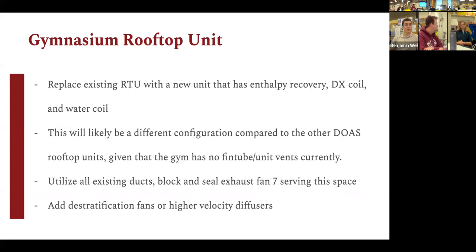So we propose adding that space also will probably have to have either higher velocity supply diffusers or destratification fans in order to get better circulation of the air in that space. And again, we're going to be sealing off the exhaust fan and just rerouting where there's already return ductwork going up to the roof for the mixed air damper. That will just serve as 100% exhaust air.